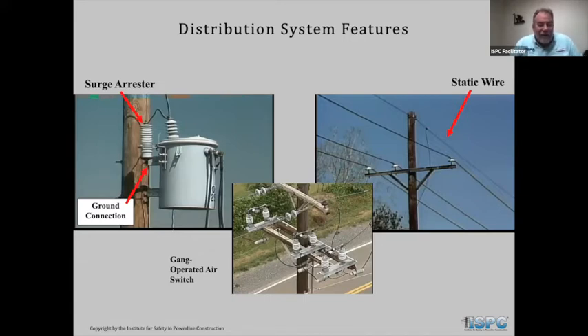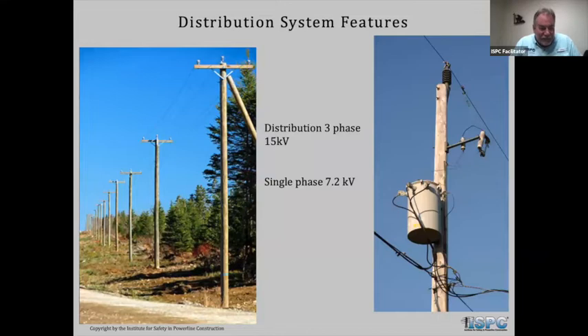The bottom part is grounded, the top part is energized, and we call them lightning arresters or surge arresters. So if there's an over voltage incident, like say a transmission phase wire falling into a distribution wire, or if lightning is in the area, these try to protect the equipment by taking all of that energy to ground. However, there are discs inside of many of these surge arresters. So when a lightning strike occurs, those discs usually explode out the bottom to try to protect the equipment. So there's another risk to your guys.